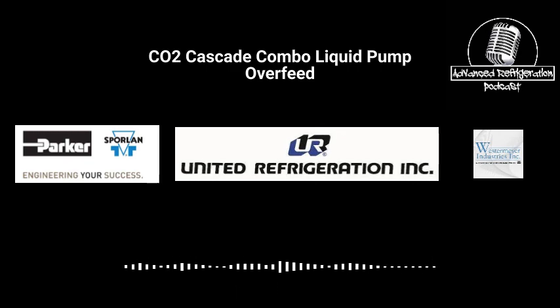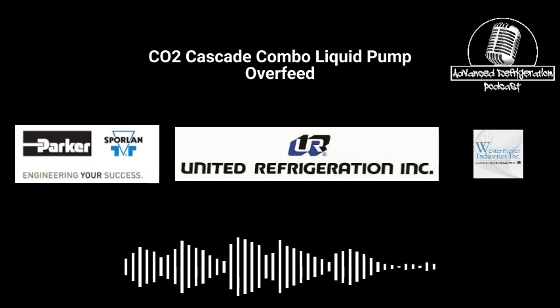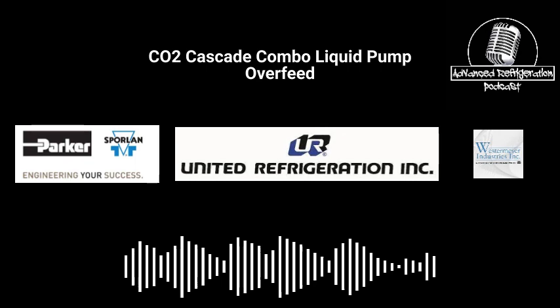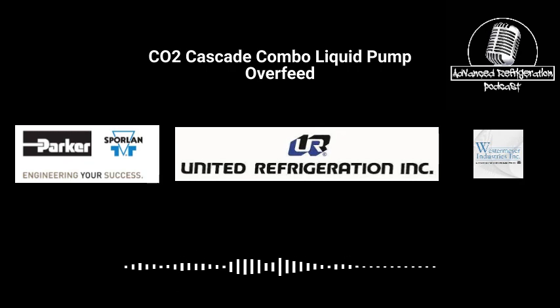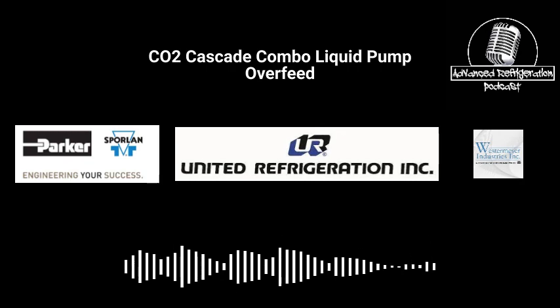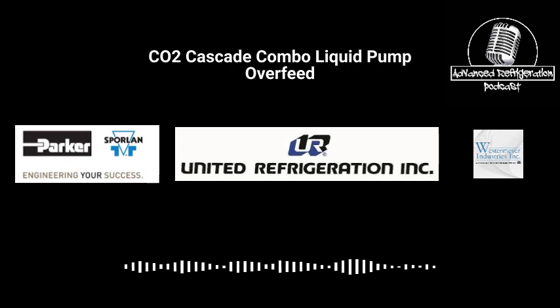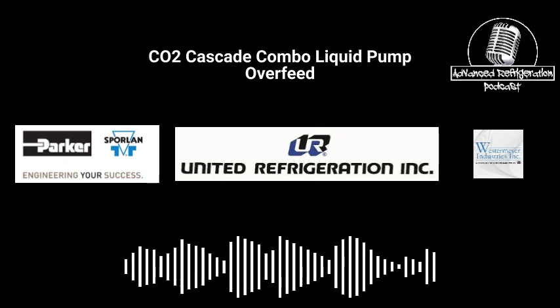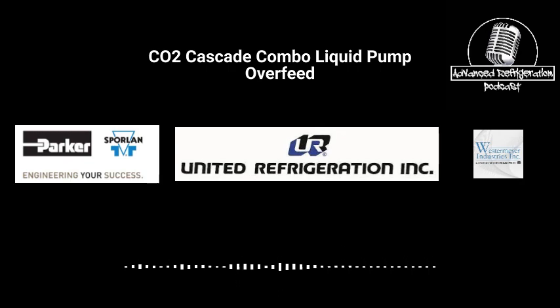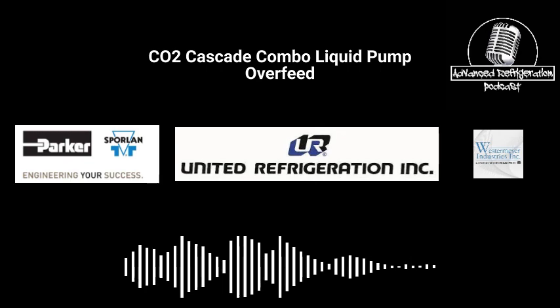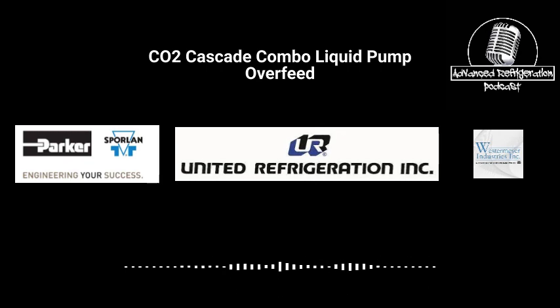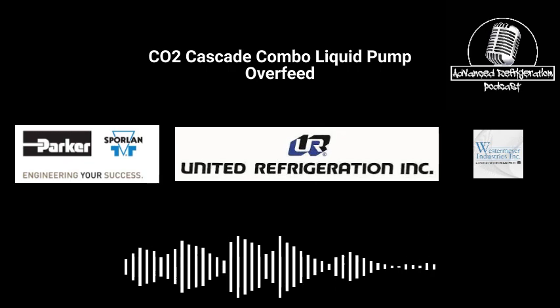So they're looking at, I think, 20 degree CO2 temperature, because then that'll take care of all your medium temps. And you might say, well, it might not be able to, because usually you have to be down to 18 degrees. You've got to remember on these liquid pump overfeeds, there's basically no expansion valve. It's just a solenoid that lets liquid CO2 in there. Remember, the lower the superheat you have, the lower the TD you'll have. So where a typical case will only have like a 10 degree TD, if you flood out that coil, you might get down to a 1 degree TD or 2 degree TD. And that's how it's able to still achieve the product temperatures needed with only a 20 degree CO2 temperature.